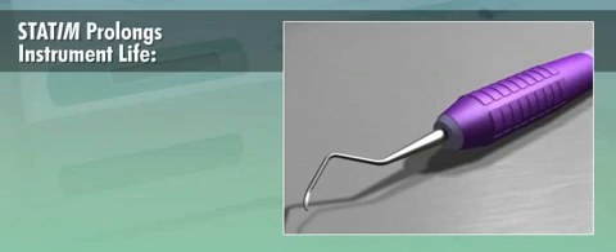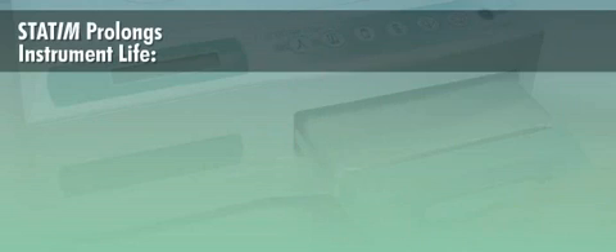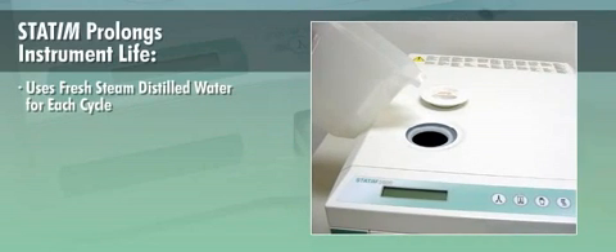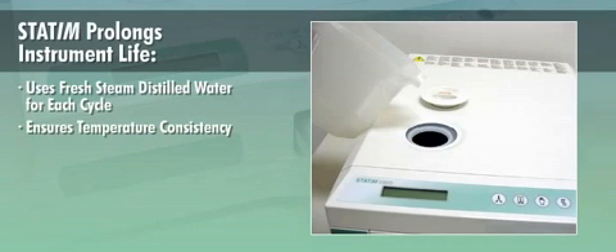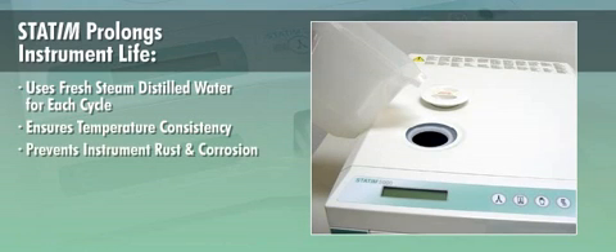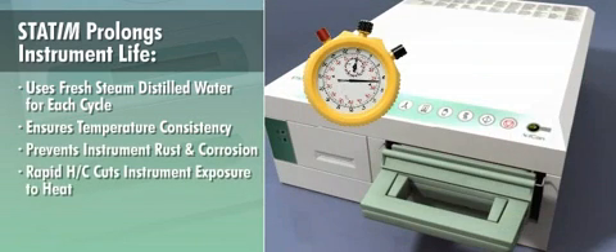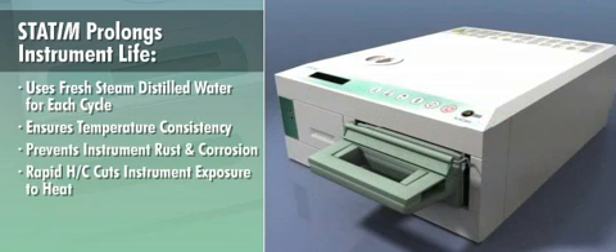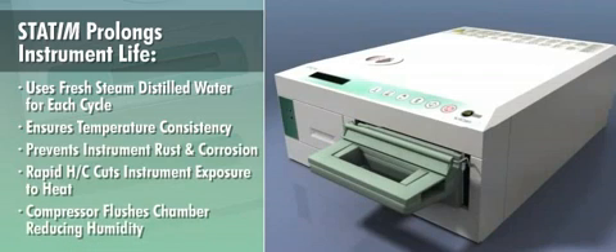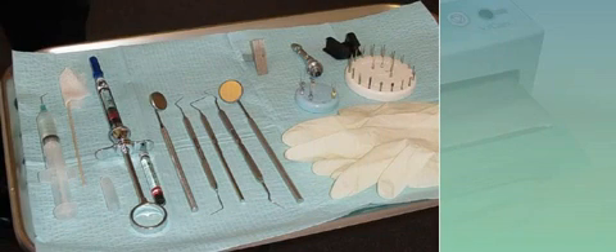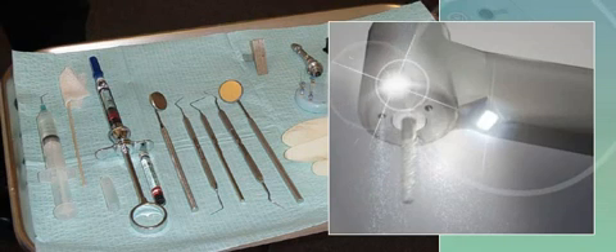STATIM prolongs the life of expensive and delicate instruments with gentle sterilization. Fresh steam distilled water is used for each cycle. STATIM's patented steam pulsing system ensures temperature consistency and it quickly expels the air that causes oxidation, preventing instrument rust and corrosion. Rapid heating and cooling dramatically cuts instrument exposure to heat, enhancing instrument longevity. Also, after sterilizing, a built-in compressor flushes the chamber with filtered dry air, further reducing humidity. Surgical instruments, scalers, handpiece turbines, fiber optics, and hinged instruments look and operate flawlessly for years.